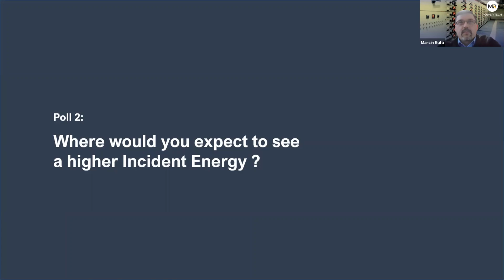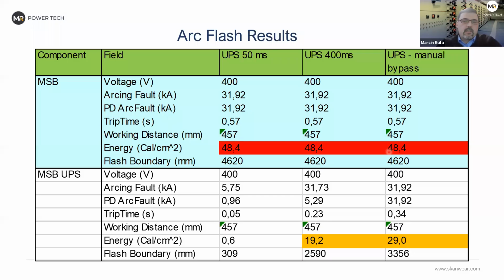but not fully true. Most of the time we'll see the problems in, as most people said, manual bypass. That's very clear because of the high energy that will be transferred, but also because of the tripping time in this specific project, of course. And UPS static was 400 milliseconds. We expect 19 calories. This is on the UPS side, and this was on the low voltage switchgear, let's say line side of the UPS and load side of the UPS. That's how we can call it.